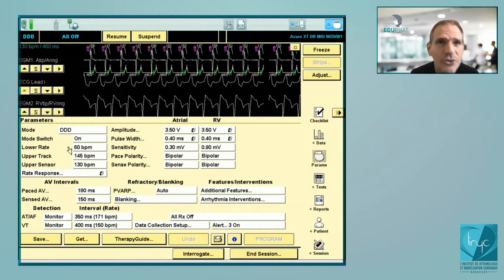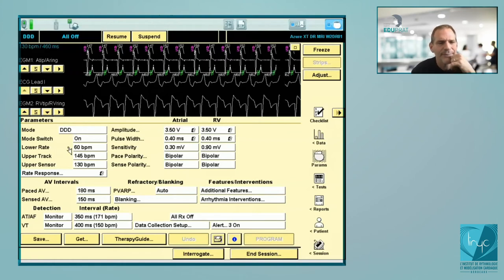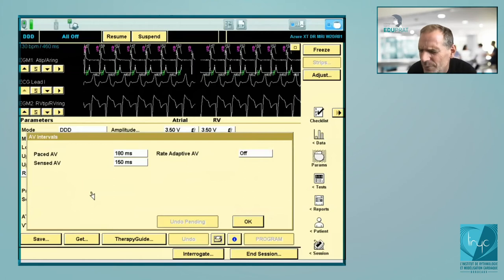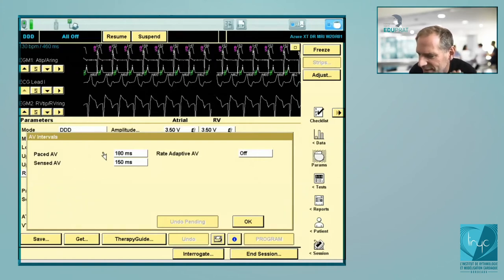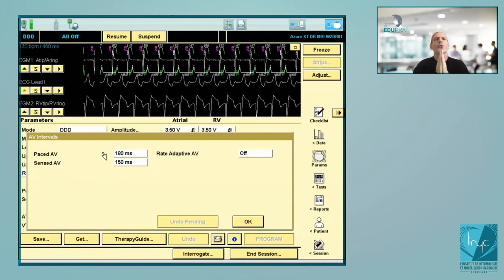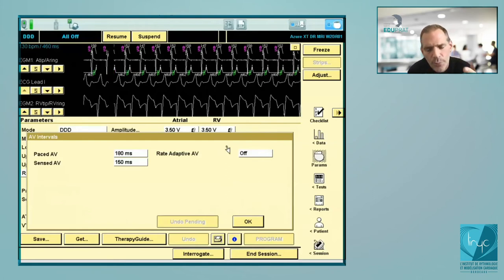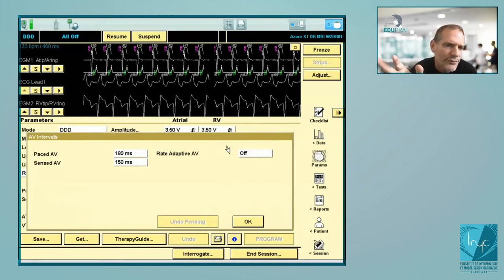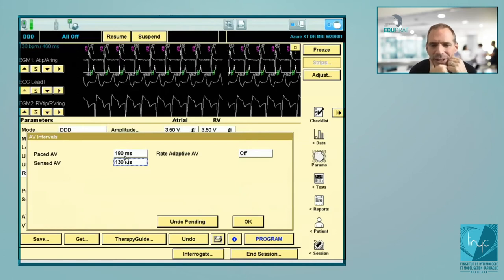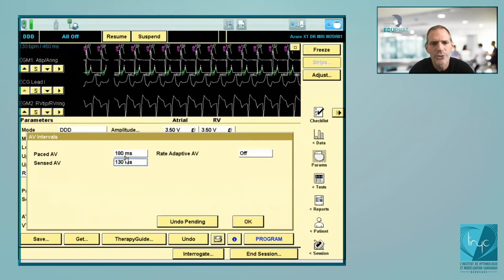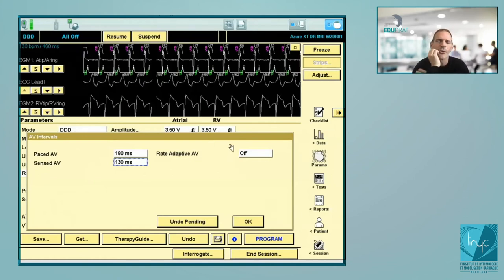Now discussing how to avoid the two-to-one block problem. The first thing you can reprogram is the sense AV delay. For two-to-one block, it's a question of sense AV — atrial sensing, ventricular pacing — not a question of paced AV. If you want to decrease the risk of two-to-one block — and this is something I systematically reprogram in a patient with complete AV block — you program a short sense AV. Nominally it's 150. You can program less, for example 130, particularly in young patients. What you need to program is the adaptive AV, which is nominally off. I systematically reprogram it on in a patient with complete AV block.